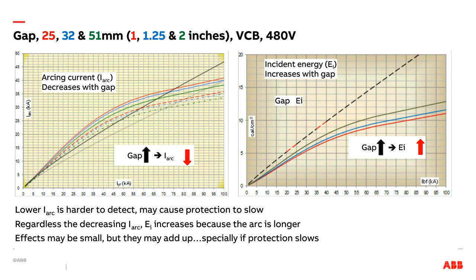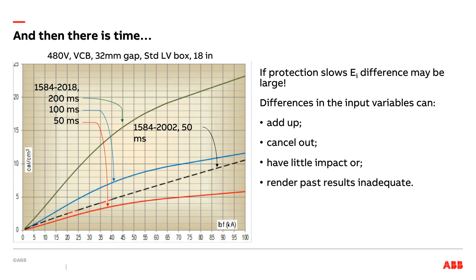So a larger gap, if you look at your old study and now you try to properly do a new analysis, you realize, oh, I should have used a larger gap. That's a more complicated situation, and that's not what we're trying to address here. We're making the assumption that the gap is going to stay the same. But the big difference here is time. 50 milliseconds, 100 milliseconds, 200 milliseconds, same conditions, VCB, 32 millimeters, 18 inches. Huge difference in energy because time ends up being an important factor, very important factor.